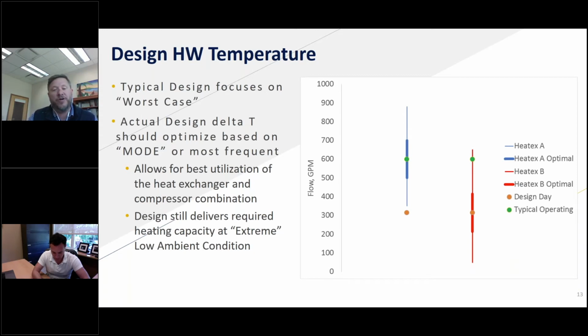It's going to take us longer to actually defrost. So there's real operational challenges and efficiency challenges that come along with what we do from a design standpoint on our unit. So if we look at this, the blue is really where we want to be. What's in a lot of cases happening today is the red line. So we're designing a unit for a design day. We're kind of fitting that into the spot from a flow perspective where it's happy.